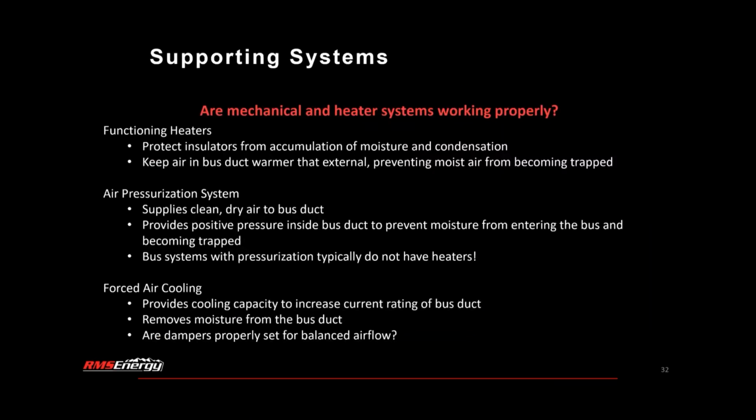It also supports keeping the internal air slightly warmer than external to prevent moist air from entering the bus and becoming trapped. So it's important to check those periodically to make sure they're functioning as intended. Air pressurization systems supply clean, dry air to bus ducts.